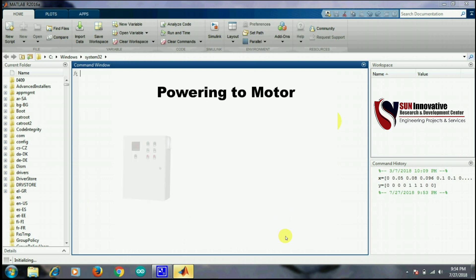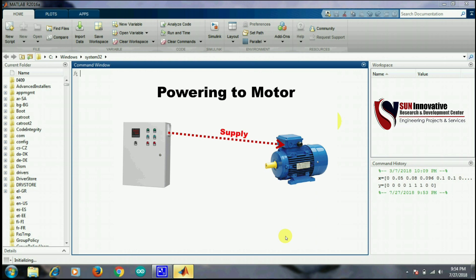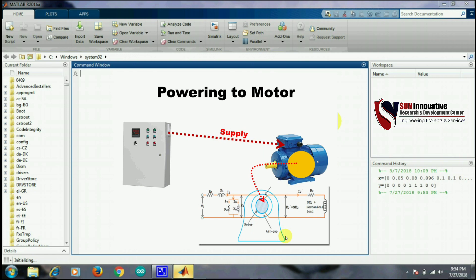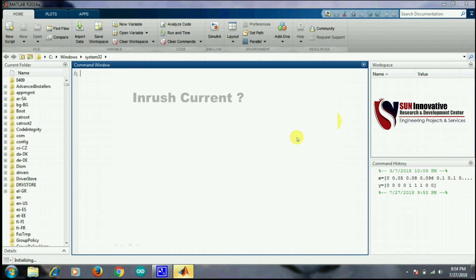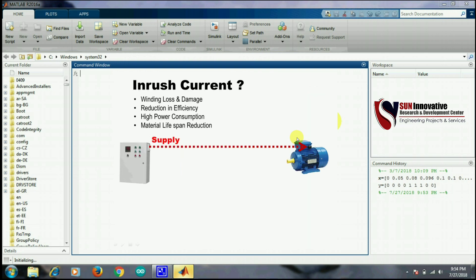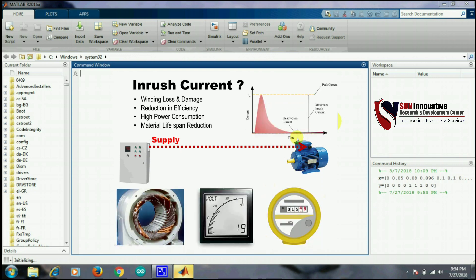When the power supply is connected to a huge inductive load like an induction motor, it will produce inrush current at the starting of the induction motor, and after that it will settle down to the rated current. As you can see in the diagram, at starting the current increases and the voltage reduces. This inrush current is associated with problems like high power consumption, winding loss, damage to insulation, reduction in efficiency, and reduction in life cycle.